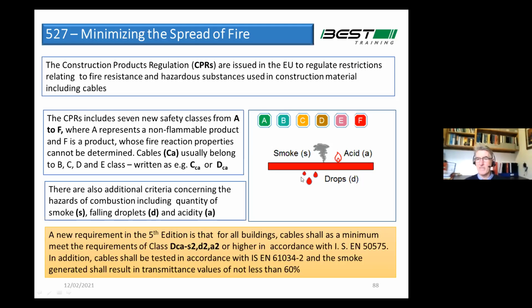So let's look at what it means. DCA is the first part of the reference. The D just stands for the fire performance. So A is a non-combustible product, if you like, and F is a product that has no rateable fire performance. And B, C, and D, it gets better. E is like PVC, D is kind of like LSZH type cables, C is higher performing LSZH cables. And to be honest with you, I don't know what B and A are like. A is effectively non-combustible, so I can't find any data on it, but I'd imagine something like bare MICC, which is a non-combustible cable, would fall into that category. But other than that, I'm not really sure if there are any cables rated ACA. The little CA in the subtext beside it just simply means cable.